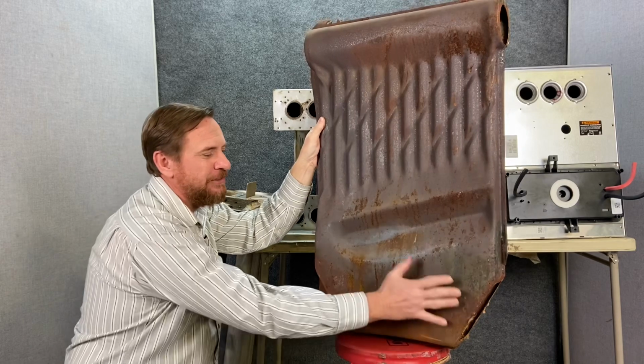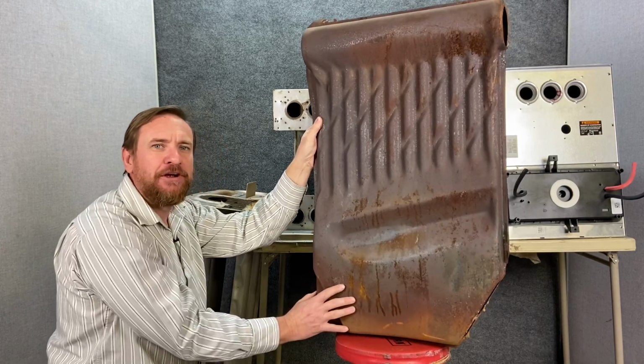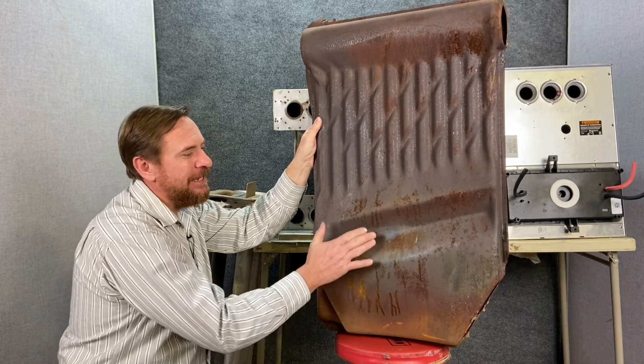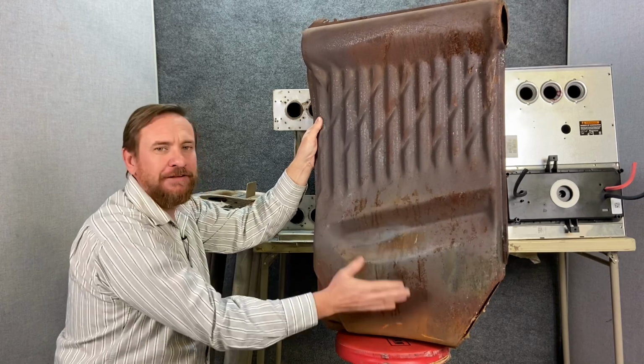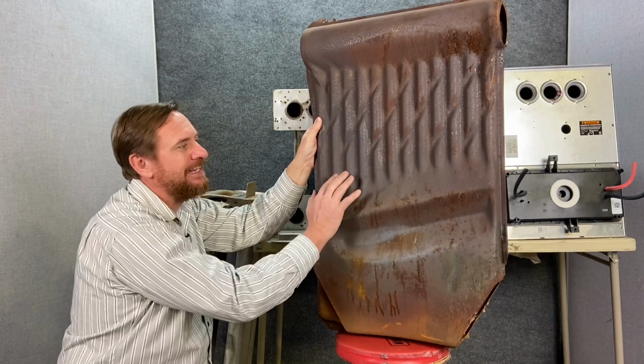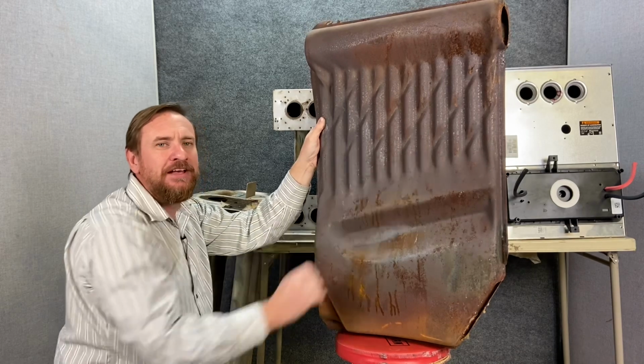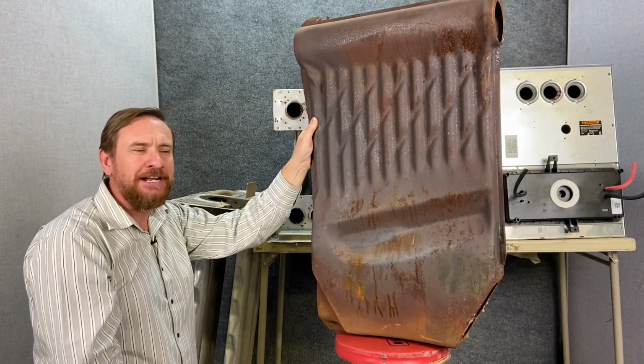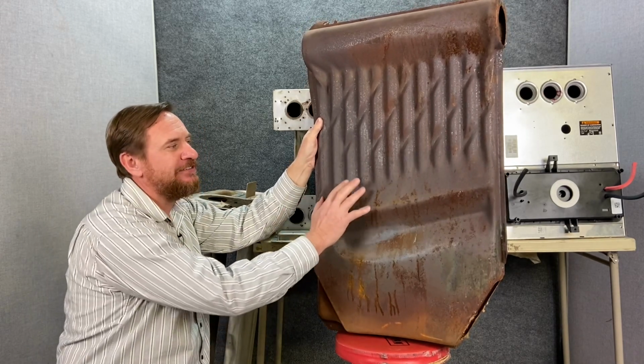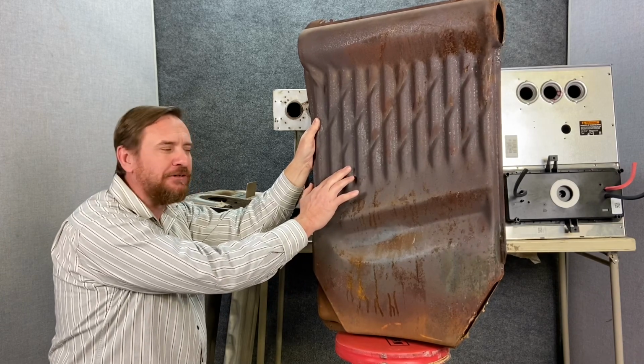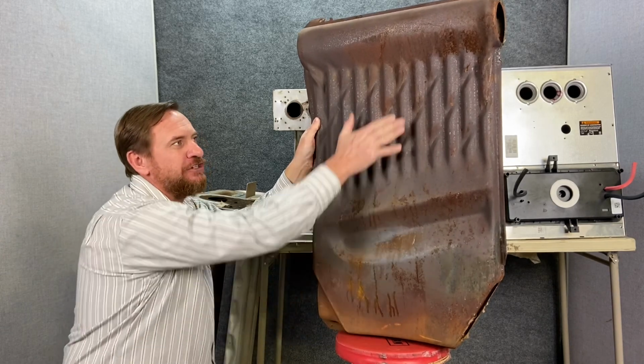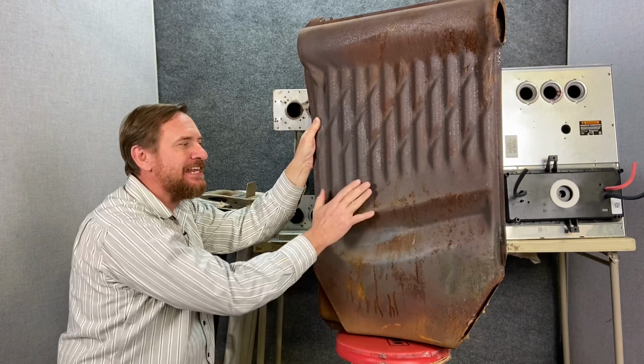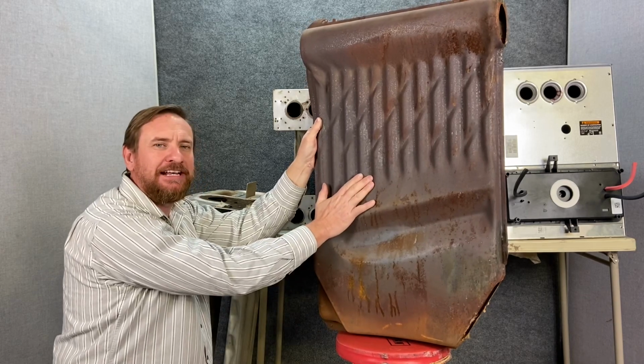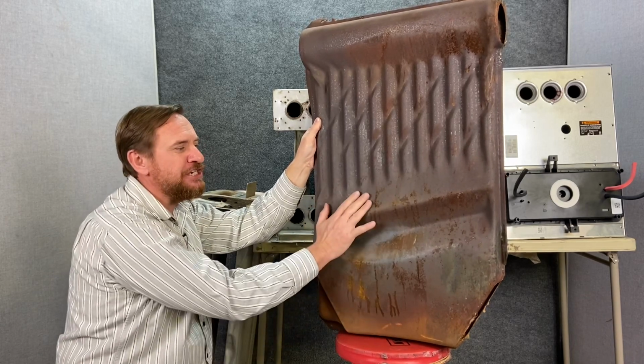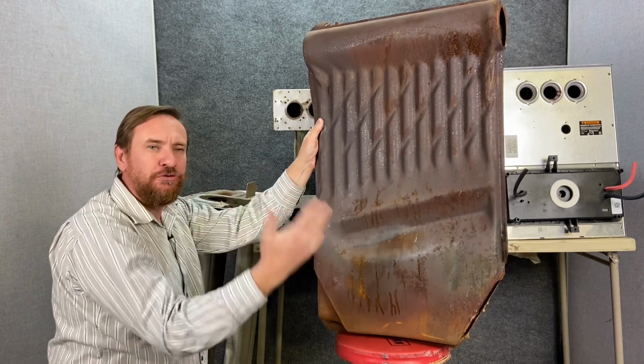Now, if you notice this heat exchanger, we have all these little grooves inside of here. The idea was that the bottom would be our combustion chamber where flames burn. Then we make the flames move, or not the flames, but the gases themselves move, and they get smaller and smaller in these chambers. This goes back to the second law of thermodynamics. We want as much of the hot gases touching as much metal as possible. Then on the outside of this heat exchanger is where the air is running. So the heat exchanger is keeping the flames and hot gases separate while also exchanging the heat through this metal to the air in the house.